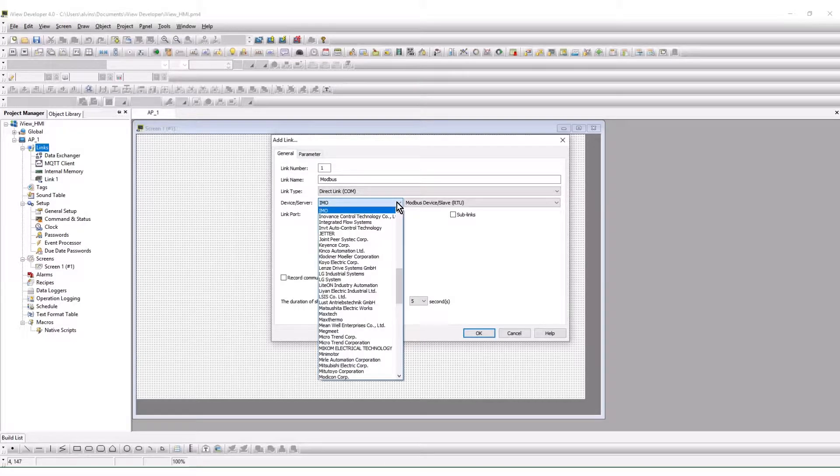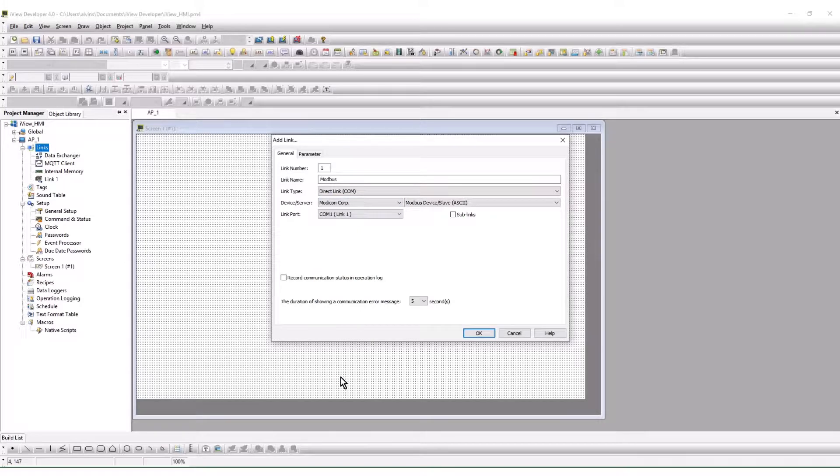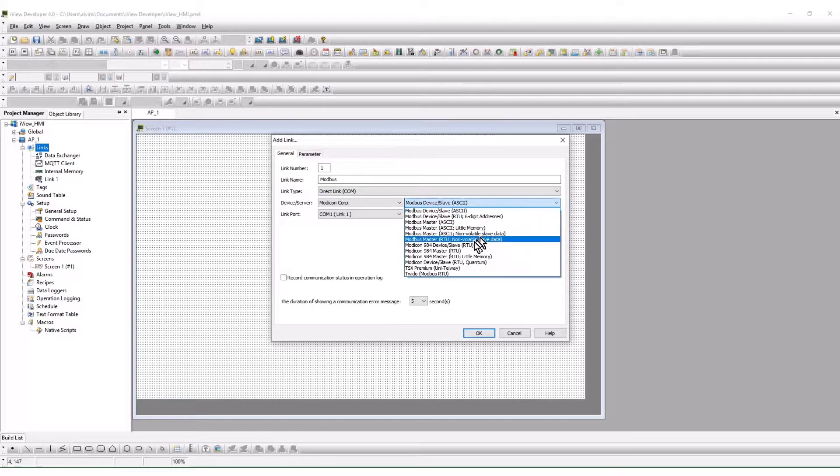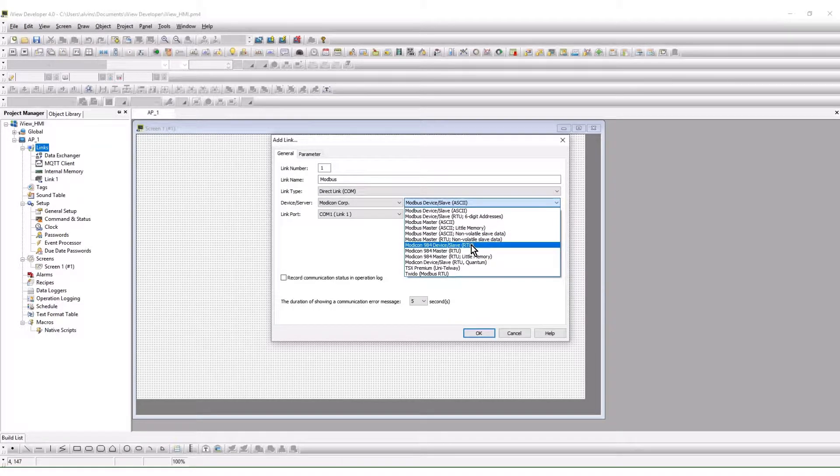The device server is the manufacturer of the connected device or the industry protocol. Modicon is where the Modbus drivers are located. To the right are the specific drivers associated with the manufacturer. This example uses Modbus 984 device slave driver as the HMI is acting as a client device or master.